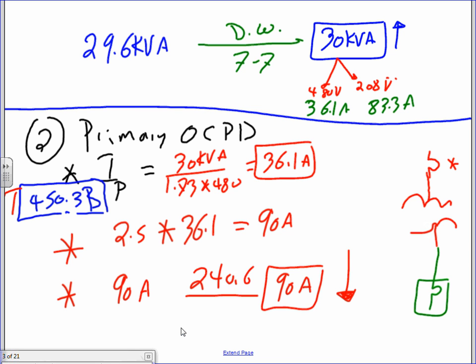So you're just saying that this was a supervised location? No, this is a non-supervised location. Are you on 450.3(B) or (A)? Oh, I was on A. Yep, go to B. When you go to 450.3(B), 450.3(B) will tell you two locations: primary only protection, or primary and secondary. If you're primary and secondary, second line, that will get you a 2.5 multiplier.